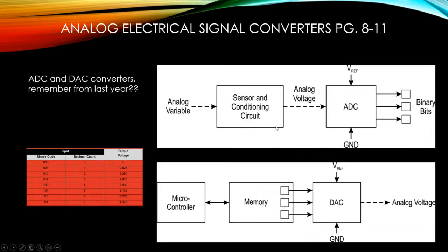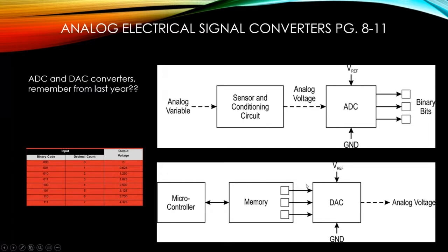Analog-to-digital signal conversion is where some of the earlier learning about resolution comes back. We take an analog signal from a transmitter and put it into a PLC, converting it from analog to digital so it can go into the processor. The processor does math, sends it out as a digital signal, which gets converted back to analog by a digital-to-analog converter, and that signal goes out to the valve.